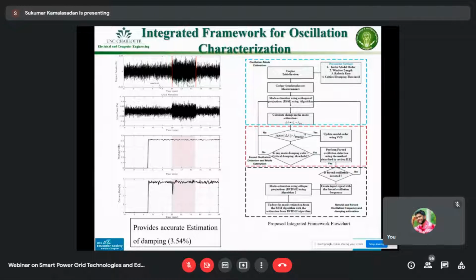Oscillations coming external to the power grid are categorized as forced oscillations. This doesn't necessarily mean they are external - it could be due to malfunction of controllers in the power plant. When this happens, you see a cyclic change, with oscillations going up and down that may or may not damp depending on the system.